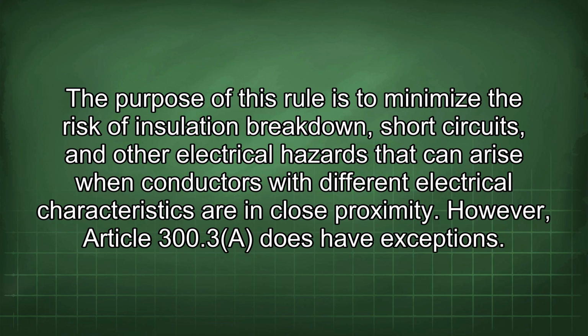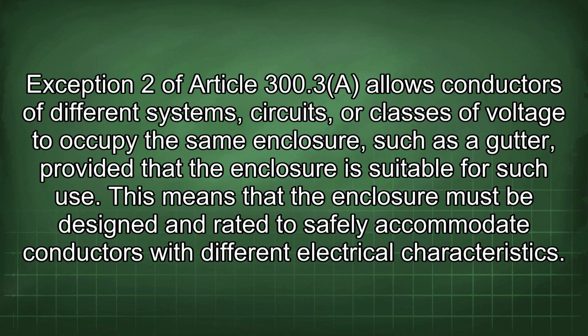However, Article 300.3 does have exceptions. Exception 2 of Article 300.3 allows conductors of different systems, circuits, or classes of voltage to occupy the same enclosure, such as a gutter, provided that the enclosure is suitable for such use. This means that the enclosure must be designed and rated to safely accommodate conductors with different electrical characteristics.